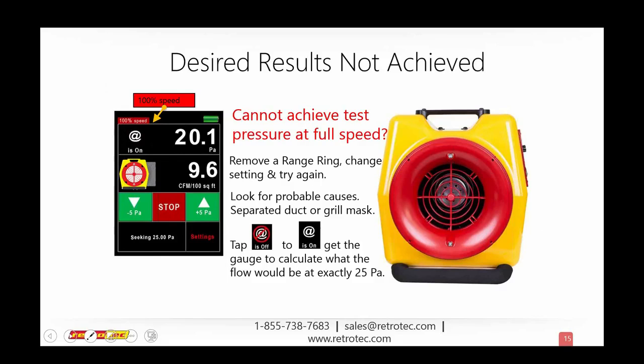It could also be the case where, simply enough, you just have a window open, or there's a piece of duct mask that has blown off. That happens a lot when you're forced to pressurize a duct system. And then of course we could also do this if we're pretty close to the desired pressure. Again, in this example it's 25, but it could be 50 or 75. We can always just use the at pressure button. When that's on, it's going to say, you're at 20 pascals, but I will give you this reading right here as if you were at 25.